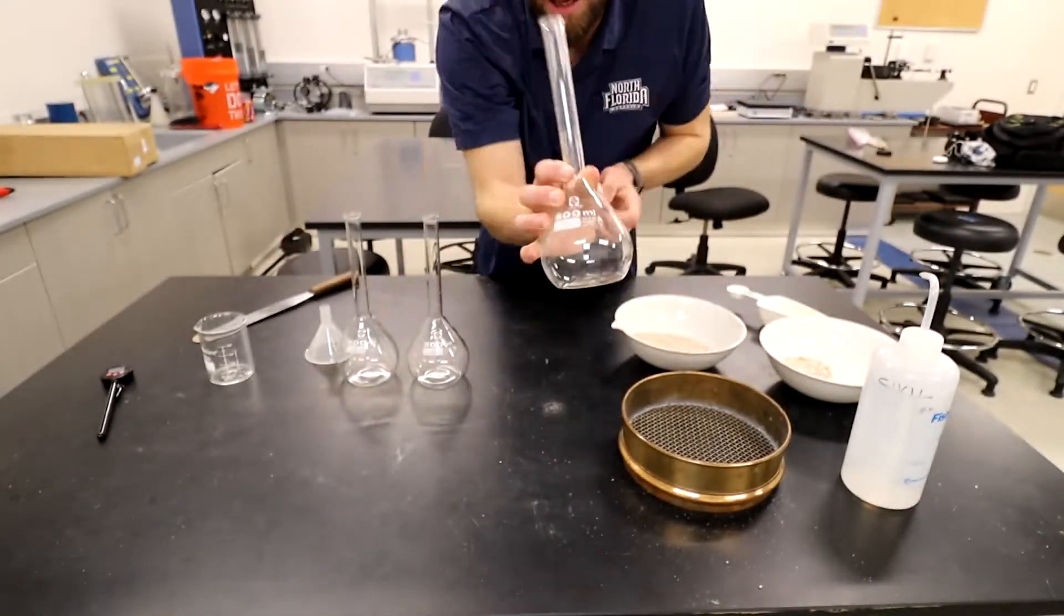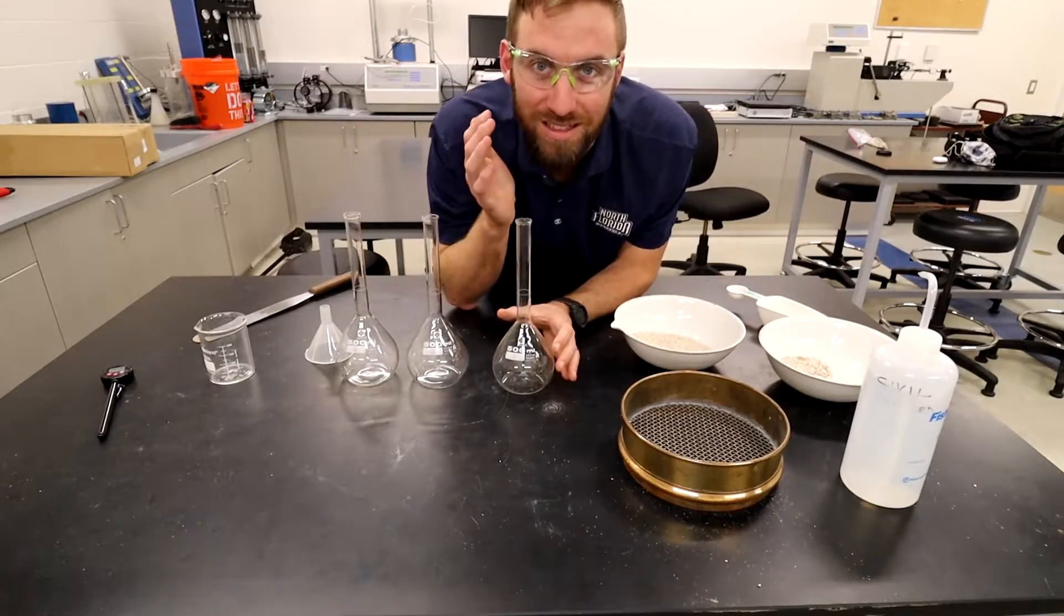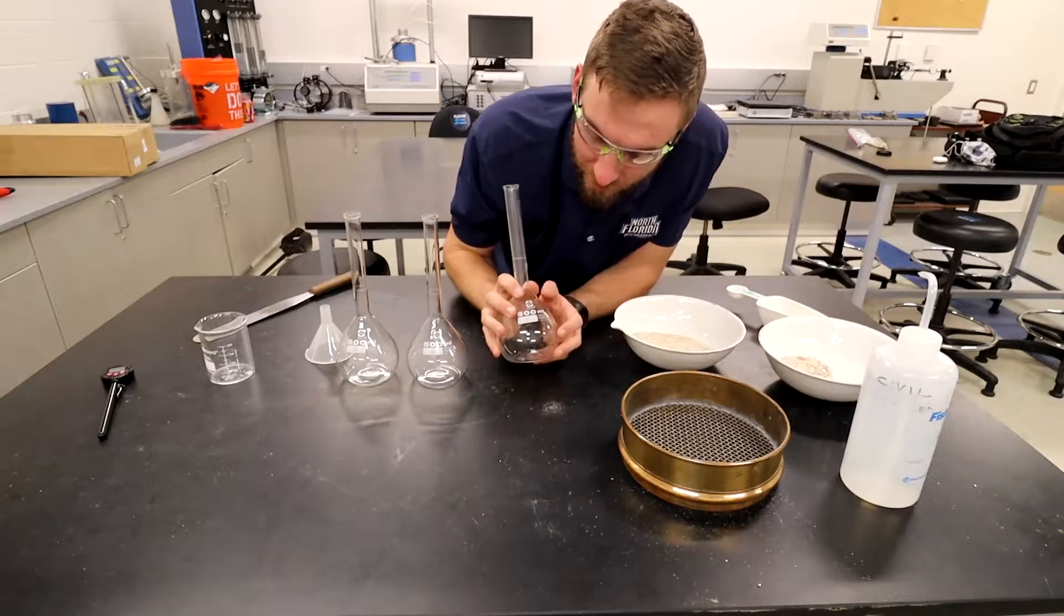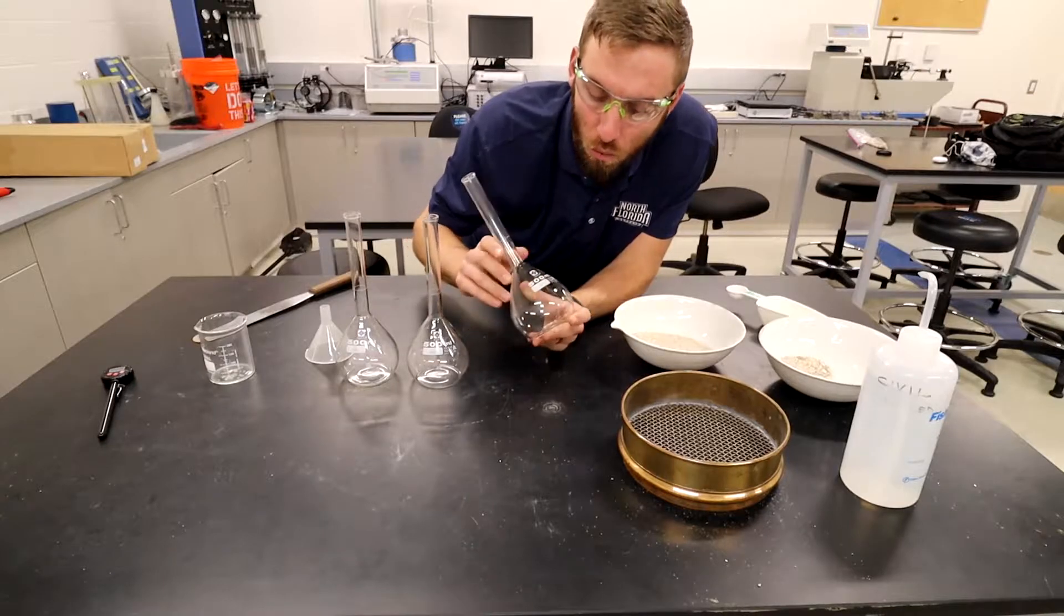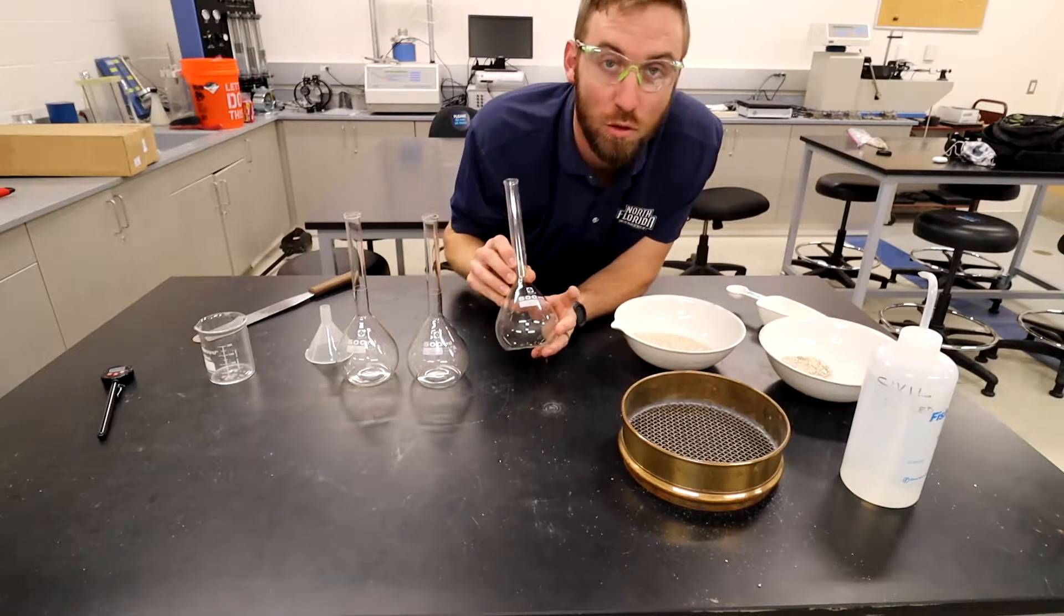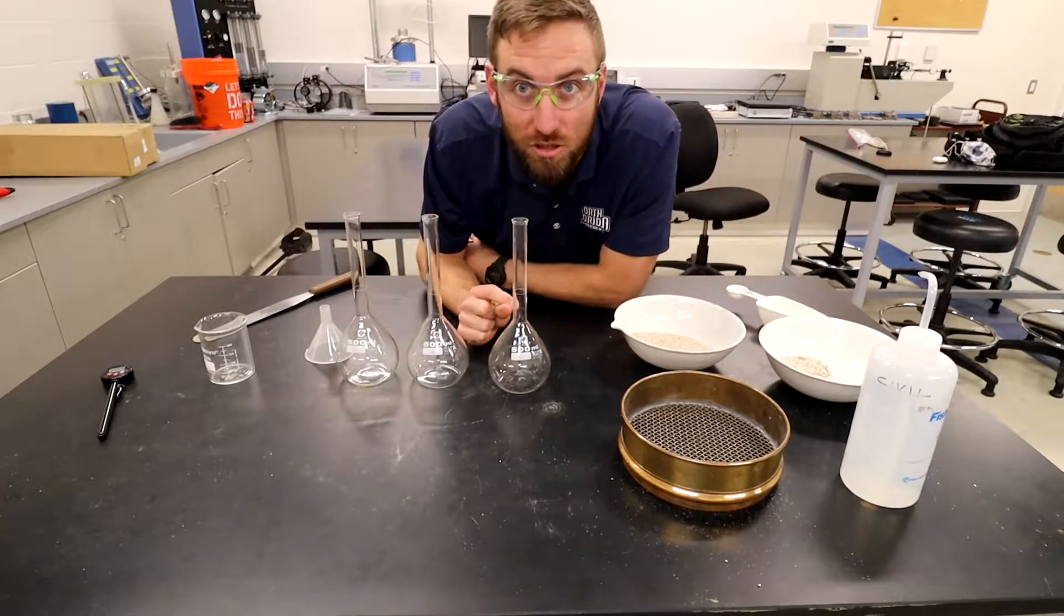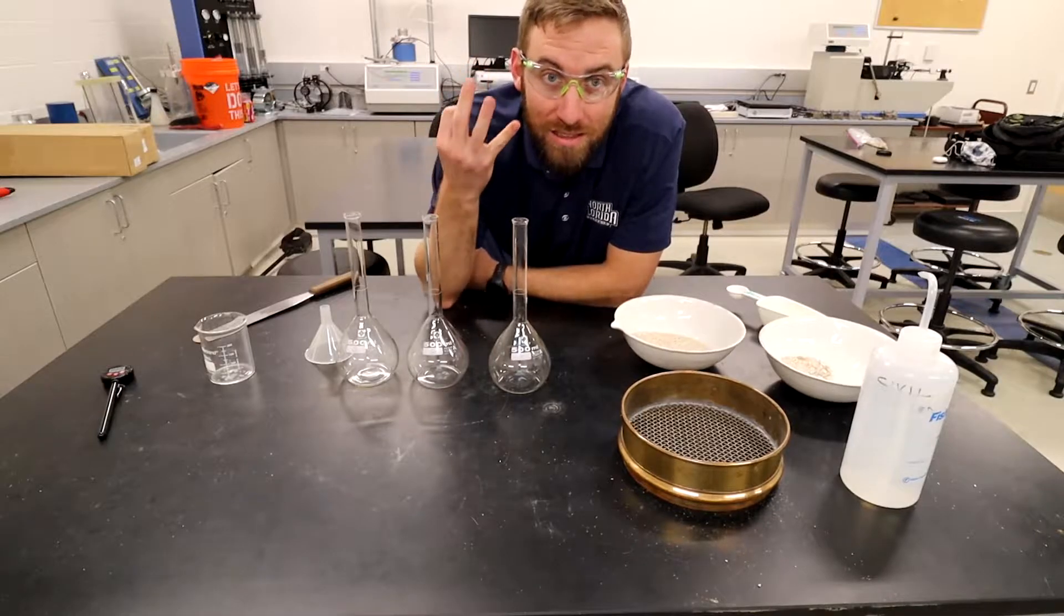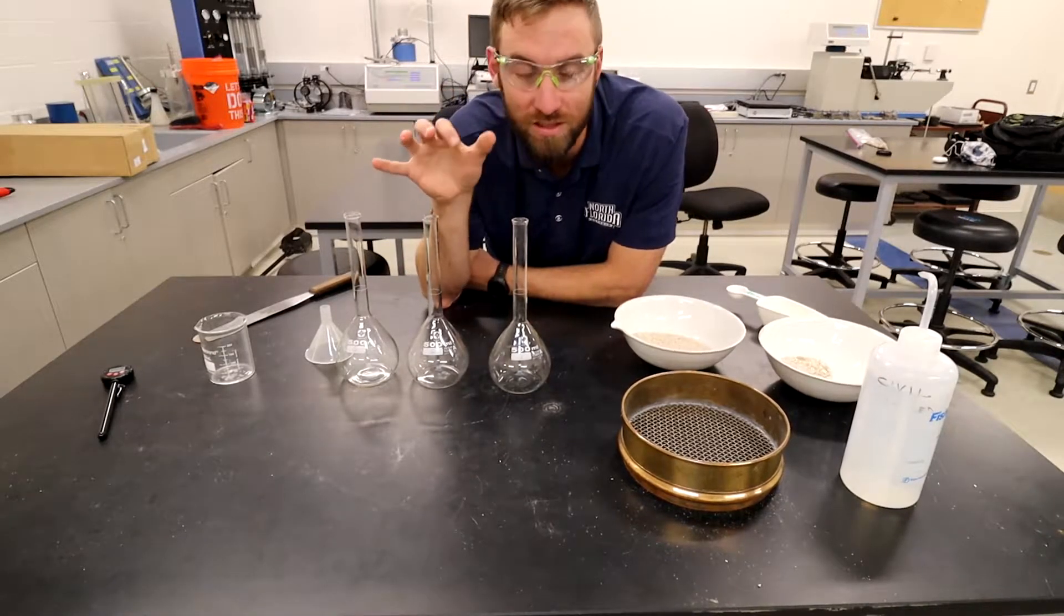There's a little white line at each one. These are basically highly calibrated containers that when filled to that line with a standard temperature of 20 degrees Celsius, we know it will be exactly 500 milliliters. We have three of them. We're going to do three tests and take the average of them just to reduce the amount of error.